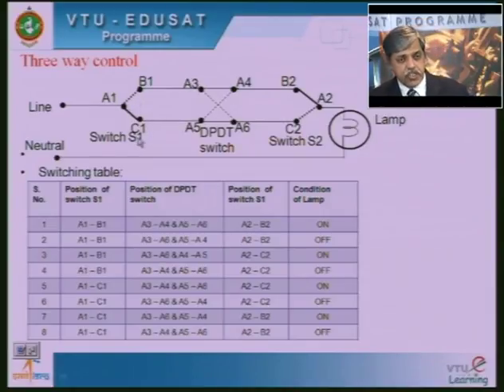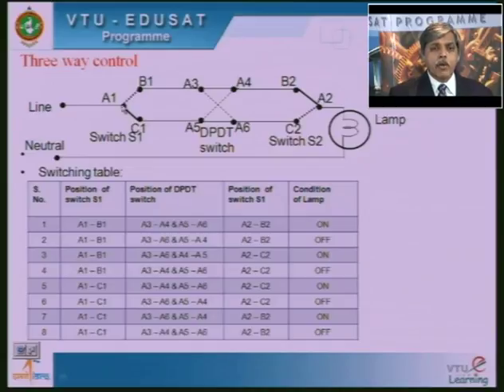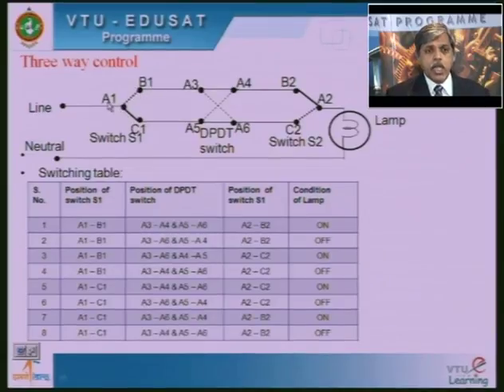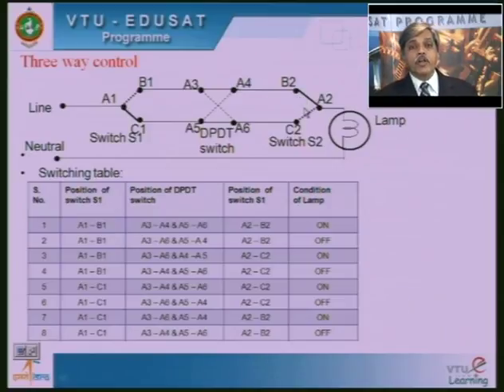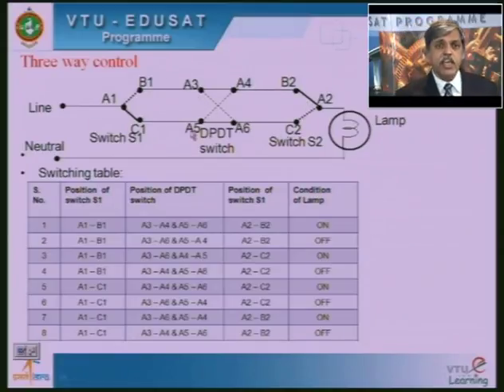If you see this two-way switch, this can be closed from A1 to B1, or A1 to C1. There are 2 positions for this, and here also I have 2 positions. So these 2 can be operated in 4 different positions. We saw that two-way control has 4 different conditions. Adding the DPDT, the number of operations will increase. So I have 2 switches, each can be closed in 2 different directions. Here it is A1 B1, A1 C1, A2 B2, A2 C2. This is A3 A4, A5 A6 or A3 A6, A5 A4.